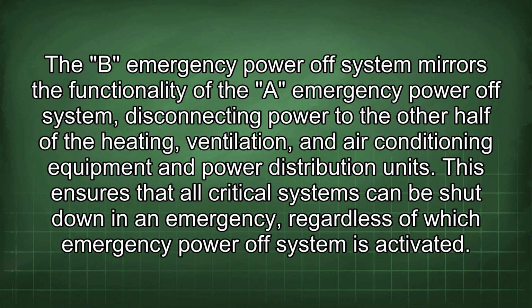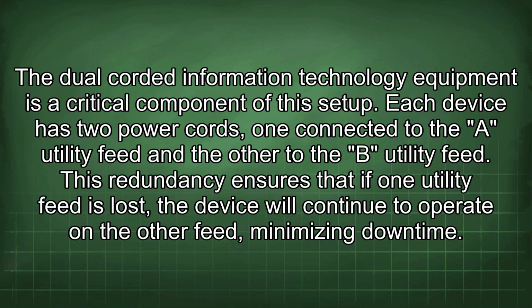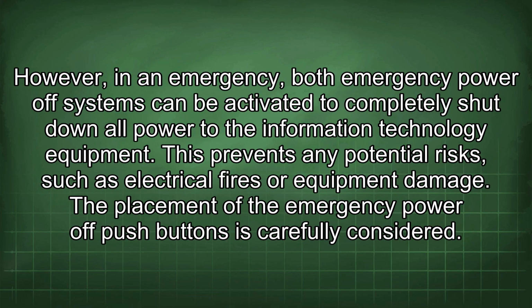The B emergency power-off system mirrors the functionality of the A emergency power-off system, disconnecting power to the other half of the heating, ventilation, and air conditioning equipment and power distribution units. This ensures that all critical systems can be shut down in an emergency, regardless of which emergency power-off system is activated. The dual-corded information technology equipment is a critical component of the setup. Each device has two power cords, one connected to the A utility feed and the other to the B utility feed. This redundancy ensures that if one utility feed is lost, the device will continue to operate on the other feed, minimizing downtime. However, in an emergency, both emergency power-off systems can be activated to completely shut down all power to the information technology equipment. This prevents any potential risks, such as electrical fires or equipment damage.